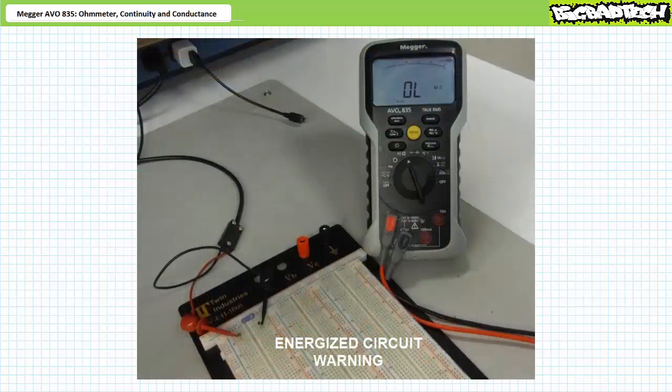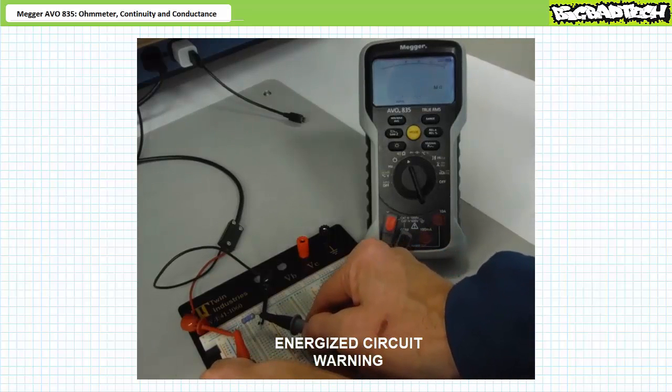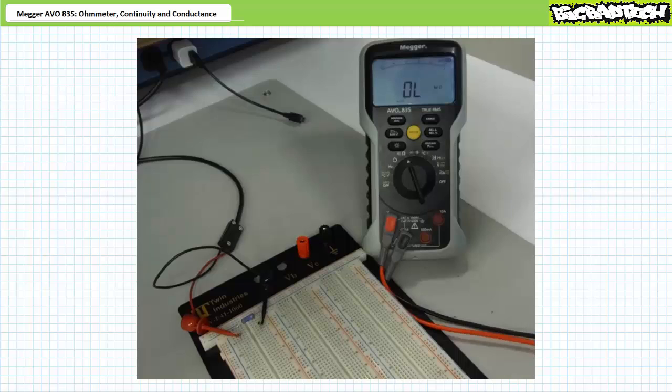Lastly, I must remind you that resistance, continuity, and conductance measurements must be taken on a de-energized circuit. In the event the Megger AVO835 detects a live circuit, the instrument will sound an audible pulse beep and flash voltage over limit on the display. This audible warning prevents an operator from damaging the instrument, the circuit, or themselves in the case of an errant energized circuit.